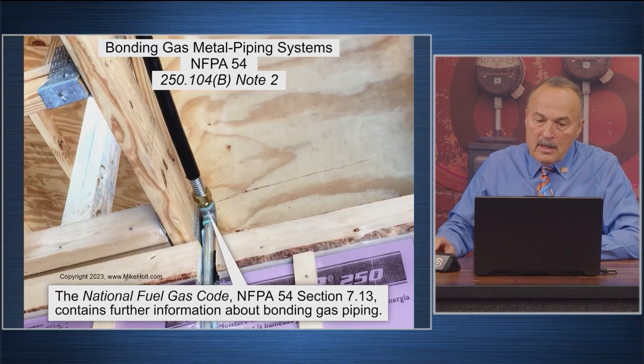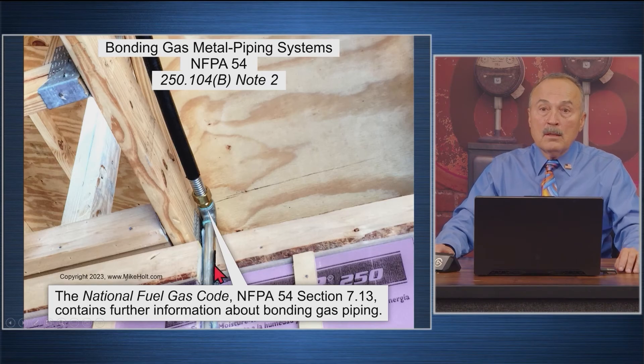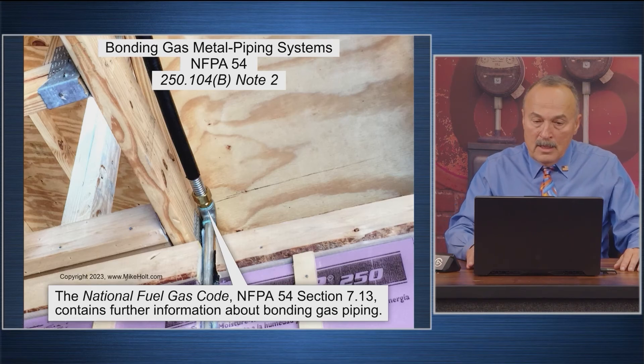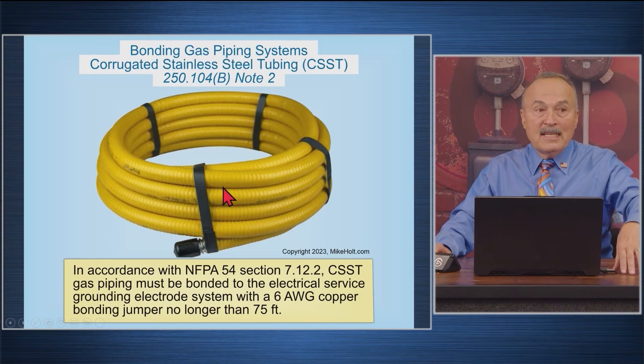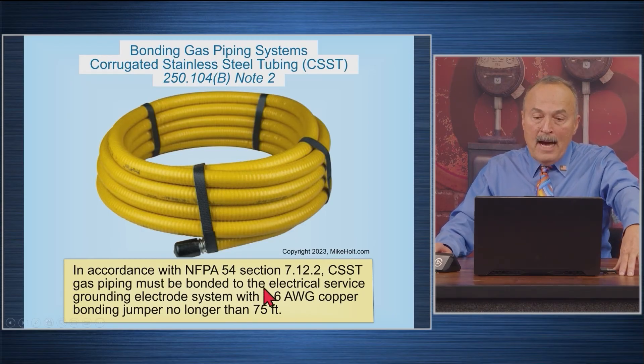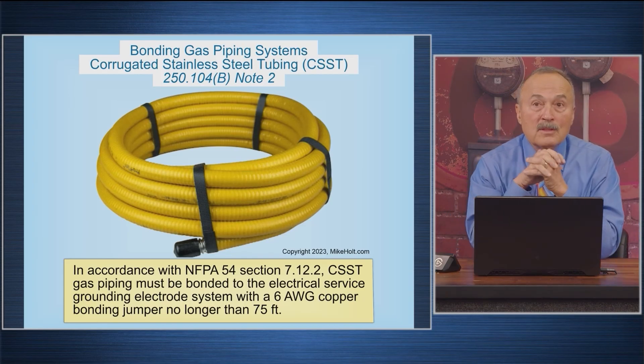To summarize: 7.12.1 (hard pipe) — don't have to worry about bonding. 7.12.2 (standard CSST) — requires bonding with a 6-gauge wire to the service grounding electrode system. 7.12.3 (arc-resistant jacket CSST) — doesn't require bonding. When you have to bond the yellow CSST, you use a 6-gauge wire and bond it to the service grounding electrode system, which is underground — the water pipe, service disconnect enclosure, grounded neutral conductor, grounding electrode conductor, or any available grounding electrode.